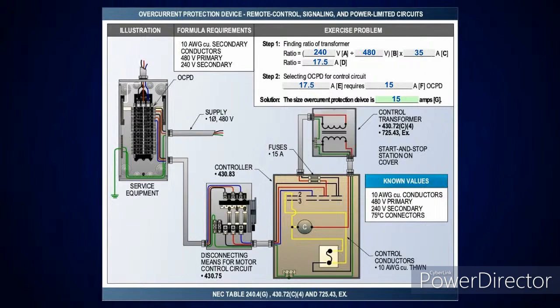Now, if I go over and I pick up my number 10 conductors and I'm terminating at 75 degrees C, it's going to tell you those number 10 conductors are good for what? 35 amps. Right. And you'll see down in the bottom right-hand side of the illustration, we're telling you our control conductors are number 10. So I'm going to get the ratio of the transformer, then multiply it by 35 amps, which is going to give me 17.5 amps.